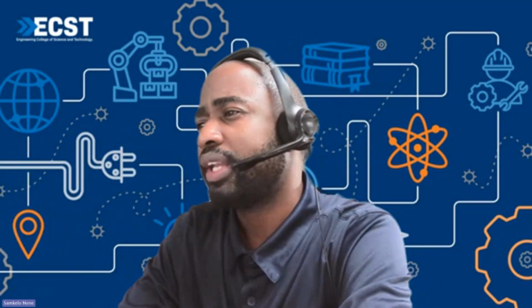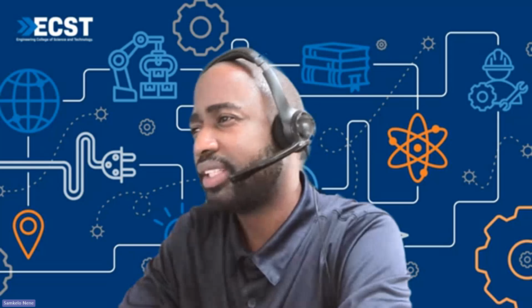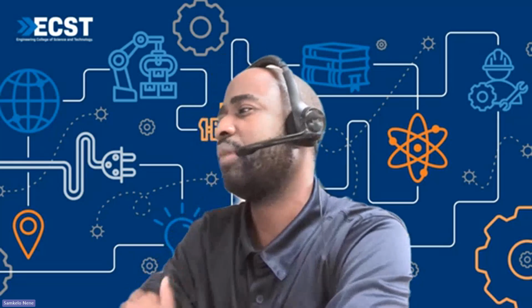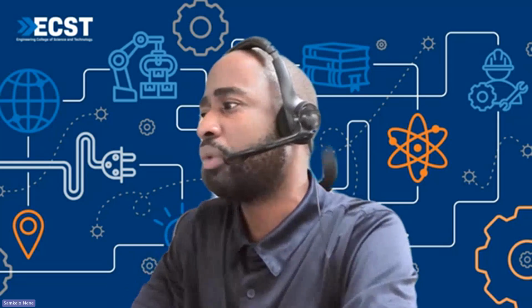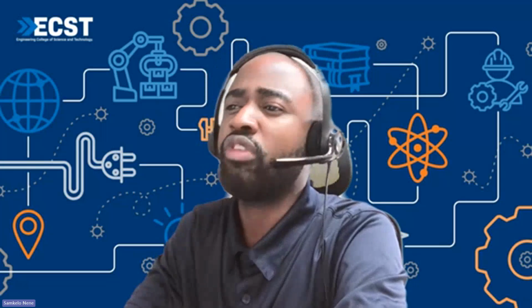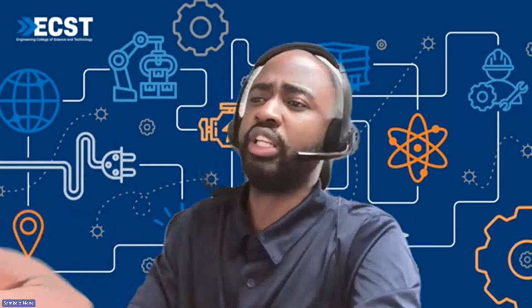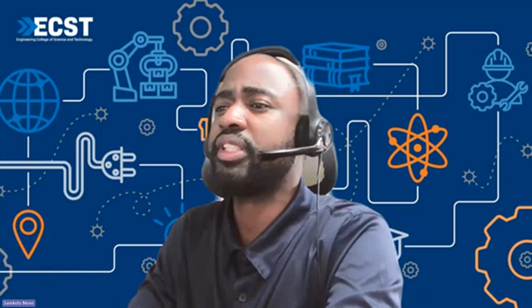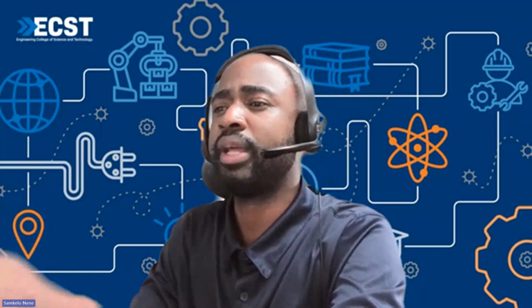And then we see on the left the capacitor banks. We did touch on the importance of reactive power. If there's over voltage, we deal with reactors. But with the capacitor banks, if there's under voltage, then we inject reactive power to balance the voltage and bring it up again.